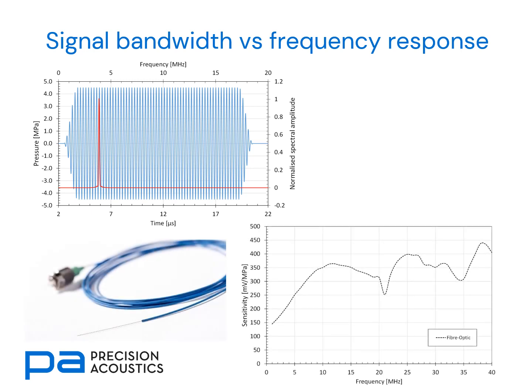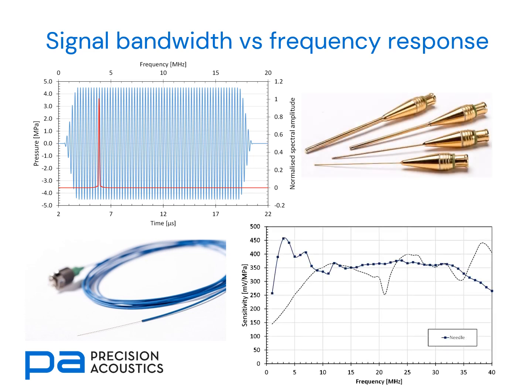However, we may be looking at a much more narrow band signal, as we often find with therapeutic ultrasound devices. You can see a much longer time duration signal but with very limited bandwidth. In this case, were we to measure the response with a fibre optic or a needle hydrophone, although these have got variations as a function of frequency, within the bandwidth of the source this variation is minimal, and we would get a very good representation of our underlying time domain function.